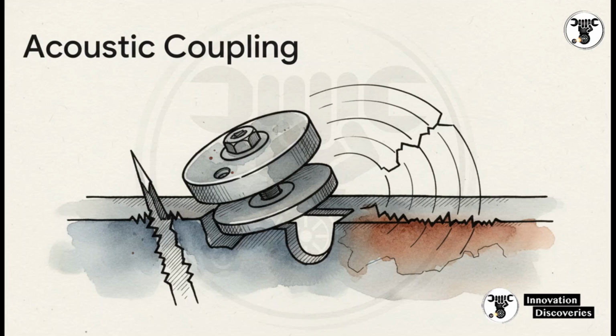If there's even a single raised burr on the metal, it creates an asymmetric clamping pivot point. And worse, tiny concave air gaps or even microscopic patches of corrosion act as literal acoustic insulators. They will completely deaden those high-frequency 10 kHz vibrations from ever reaching the crystal.